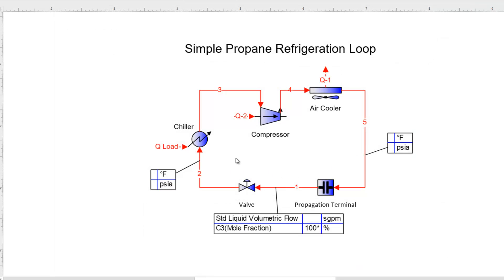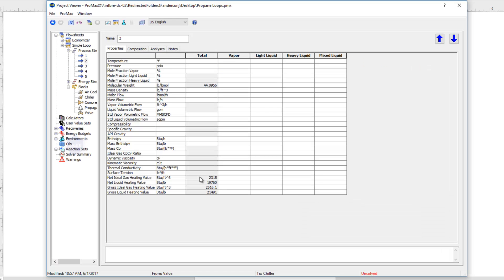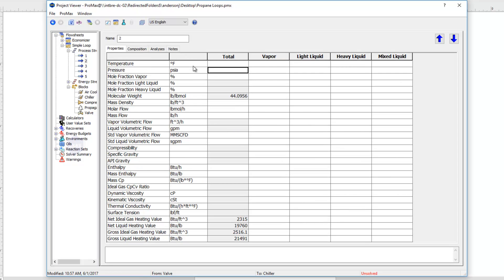The next block we run into is our valve, and this valve's job is to drop our pressure low enough that we can achieve the low temperatures we need in order to do our chilling. In the stream coming out of the valve, I could either type in a pressure if I know the pressure I want, or if I'm aiming for a particular temperature I could type that in instead. For example, if I needed to get my propane down to negative 20 degrees because the process fluid I'm cooling is negative 10 degrees with a 10-degree approach, I could just type that temperature in directly and Promax will calculate the pressure that my valve needs.